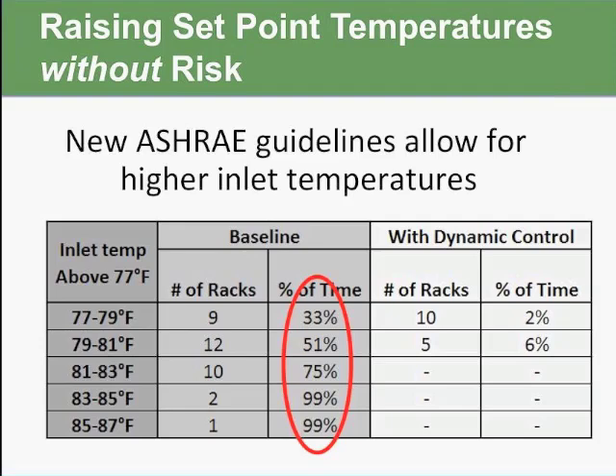And that's going to introduce a lot of risk to your equipment because you're not controlling that high endpoint temperature. But with the dynamic control, you can sit at a steady 77 degrees with little risk to your equipment. And as you can see, a very few number of racks were above that 77 degrees, but for a very, very small percentage of time. So it's a very tightly controlled environment that reduces your risk, even at that higher inlet temperature. So significantly saving a lot of energy and energy cost savings there.